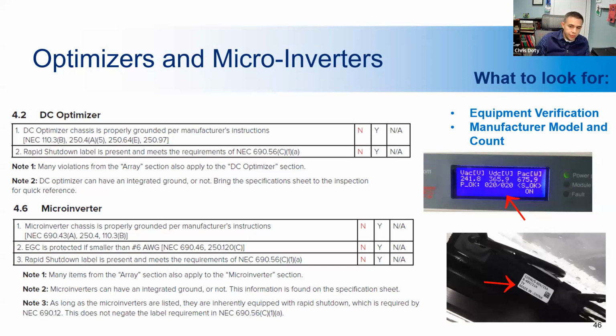They both give module level control, and they have similar requirements in the code. This is the section for that in the checklist. You can see it's pretty short, but they are pretty similar. It requires you to look for not only equipment verification, but also other details like conductor type, proper grounding, etc. And the notes at the bottom describe important details such as labeling requirements for rapid shutdown. And something to keep in mind is, even though microinverter systems meet rapid shutdown requirements by design, they all have it included in them, they still require proper labeling.